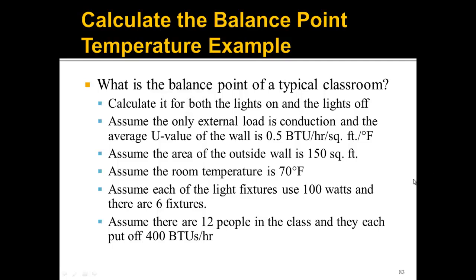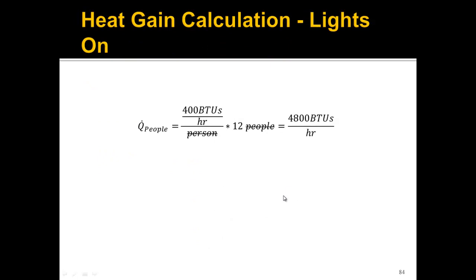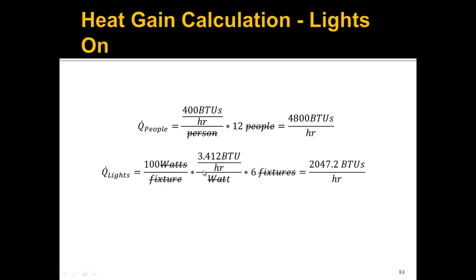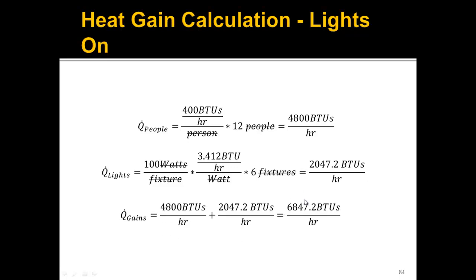Now that we know our assumptions, let's do the heat gain calculations for lights on. The people generate 400 BTU per hour per person times 12 people, giving 4,800 BTU per hour. The lights are 100 watts per fixture, converted to BTU per hour, multiplied by 6 fixtures. Adding people and lights together gives a total heat gain of 6,847.2 BTU per hour.